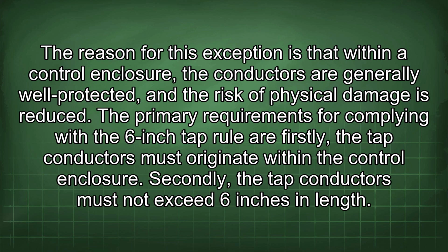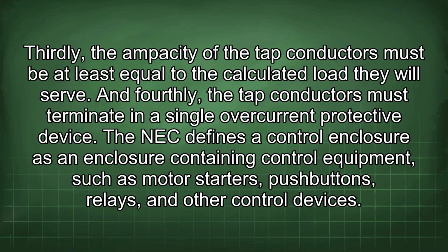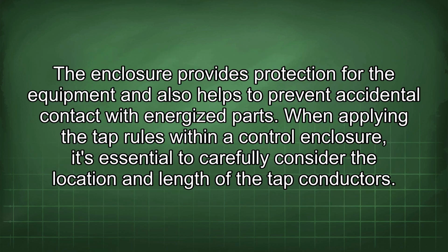The primary requirements for complying with the 6-inch tap rule are: firstly, the tap conductors must originate within the control enclosure. Secondly, the tap conductors must not exceed 6 inches in length. Thirdly, the ampacity of the tap conductors must be at least equal to the calculated load they will serve. And fourthly, the tap conductors must terminate in a single overcurrent protective device. The NEC defines a control enclosure as an enclosure containing control equipment, such as motor starters, push buttons, relays, and other control devices. The enclosure provides protection for the equipment and also helps to prevent accidental contact with energized parts.